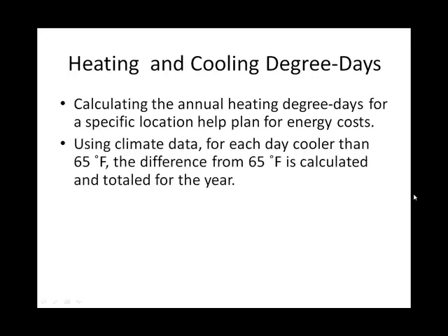So first, starting with heating degree days, now I'm not sure I necessarily agree with this, but if you take as the baseline 65 degrees Fahrenheit, for each day colder than 65 degrees Fahrenheit, you take the difference and then add up all of those differences throughout the year. And they use historic, climatic data to calculate this.